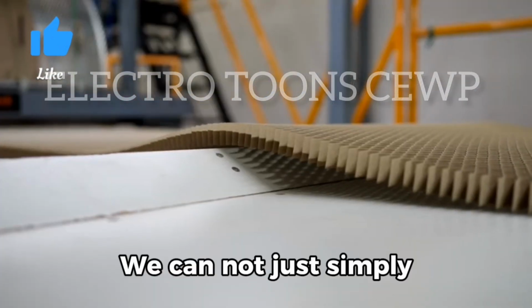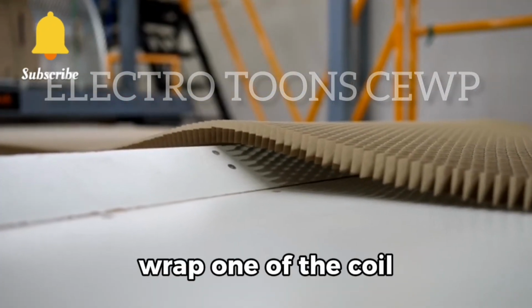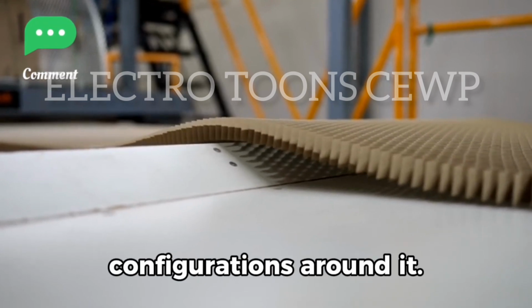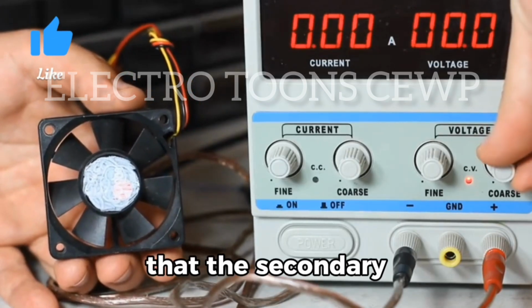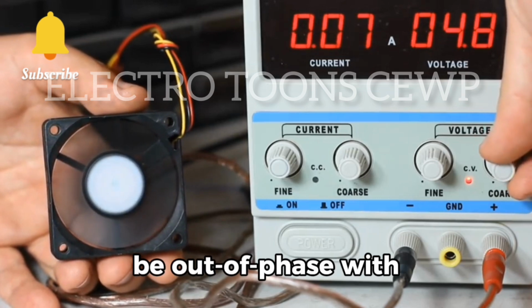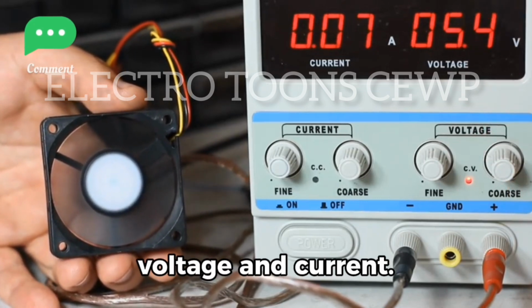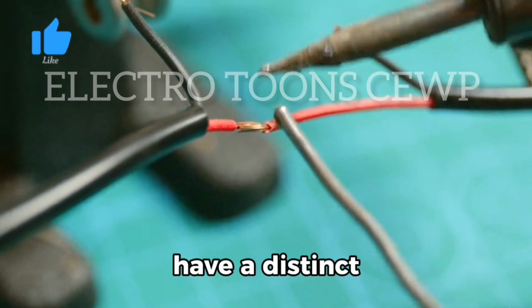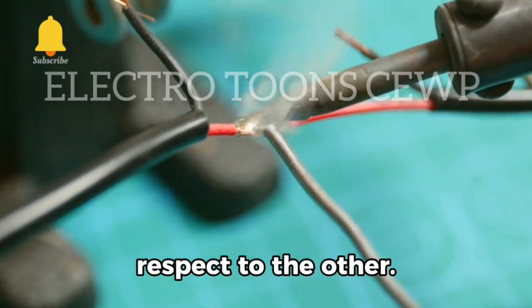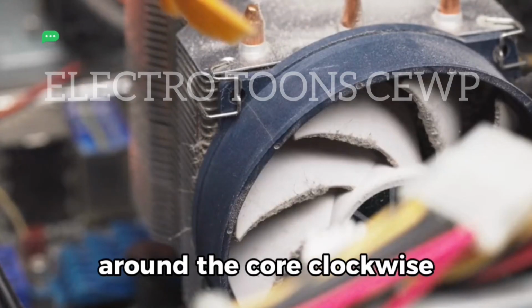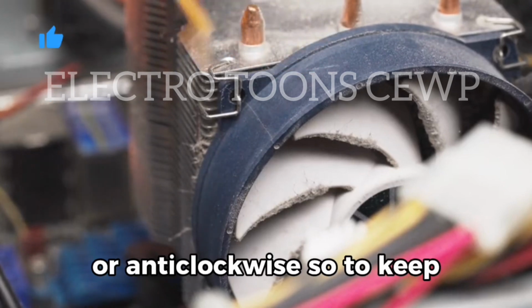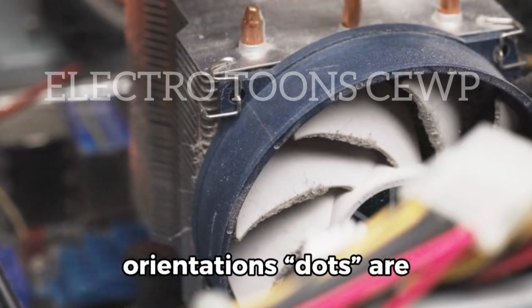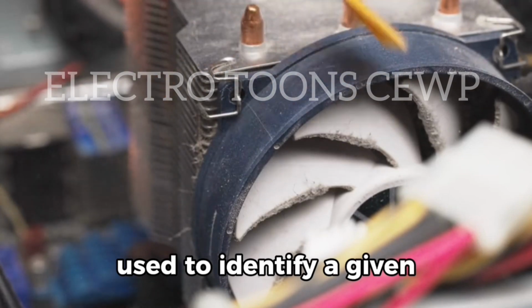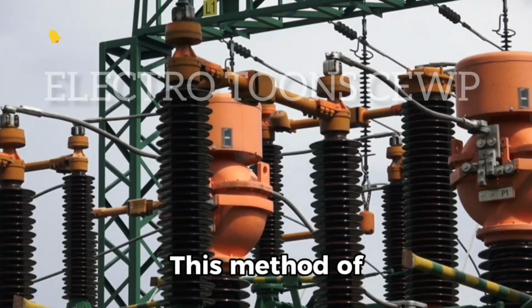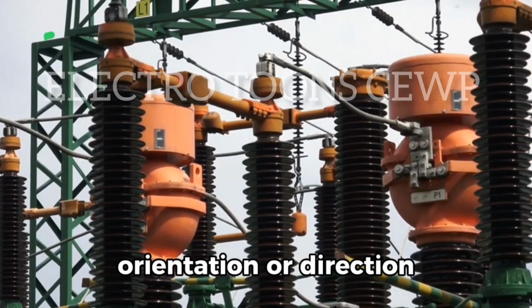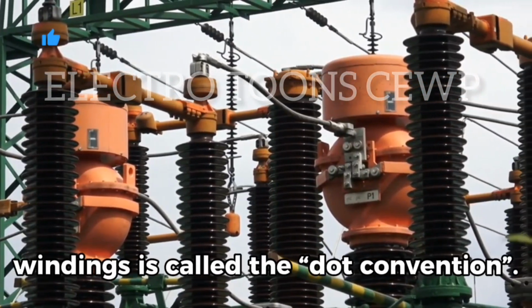Transformer orientation. We cannot just simply take a laminated core and wrap one of the coil configurations around it. We could, but we may find that the secondary voltage and current may be out of phase with that of the primary voltage and current. The two coil windings do have a distinct orientation of one with respect to the other. Either coil could be wound around the core clockwise or anti-clockwise, so to keep track of their relative orientations, dots are used to identify a given end of each winding. This method of identifying the orientation or direction of a transformer's windings is called the dot convention.